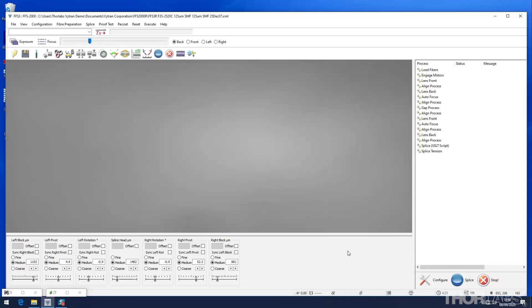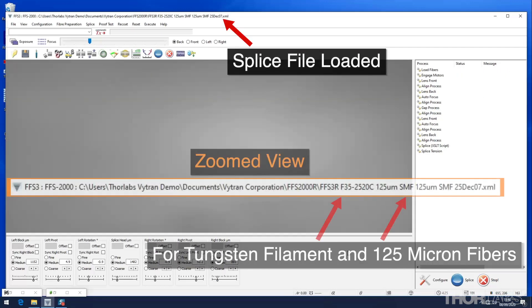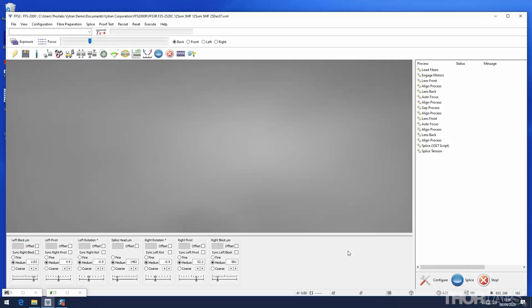Splice files for typical filament types and fiber diameters are pre-installed on the computer that ships with the unit. The parameters for a specific splice file can be viewed by going to the splice menu and selecting splice properties.